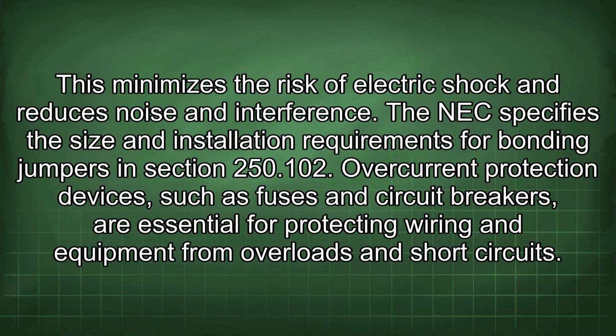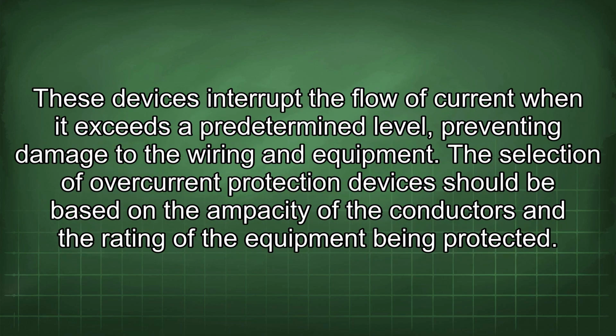Overcurrent protection devices, such as fuses and circuit breakers, are essential for protecting wiring and equipment from overloads and short circuits. These devices interrupt the flow of current when it exceeds a predetermined level, preventing damage to the wiring and equipment. The selection of overcurrent protection devices should be based on the ampacity of the conductors and the rating of the equipment being protected.